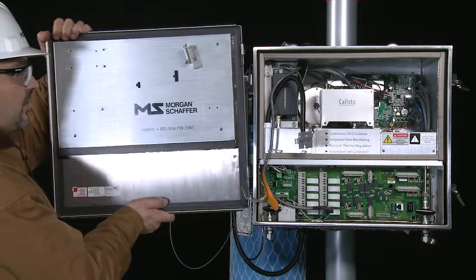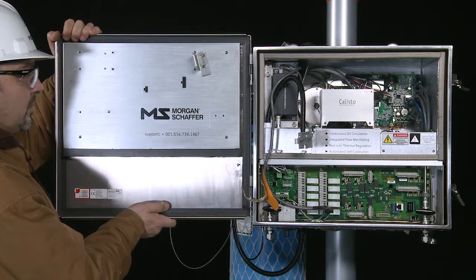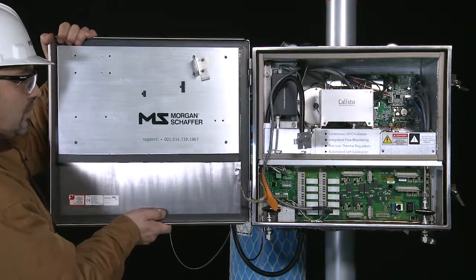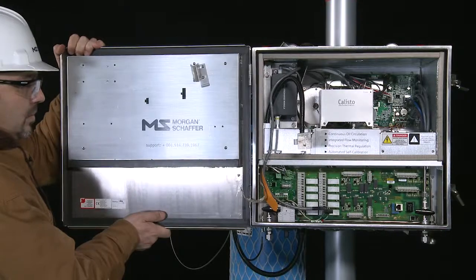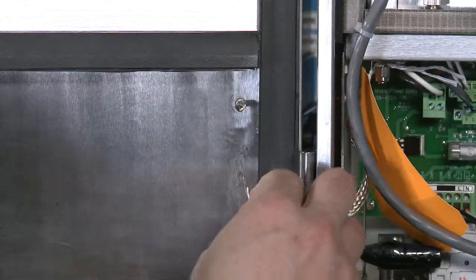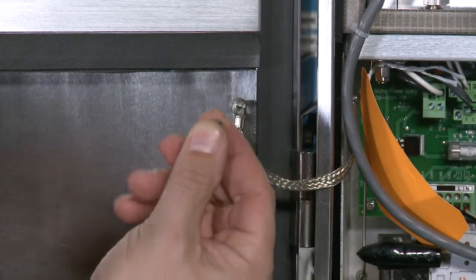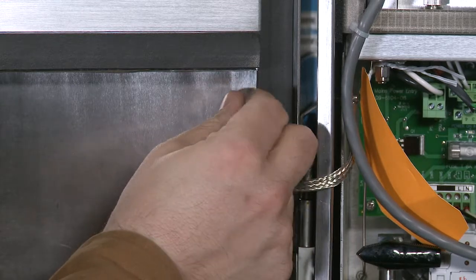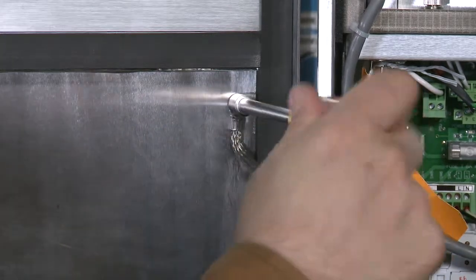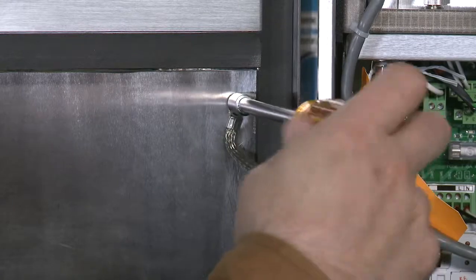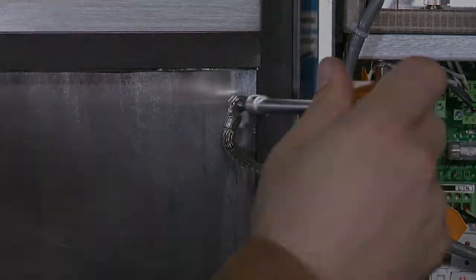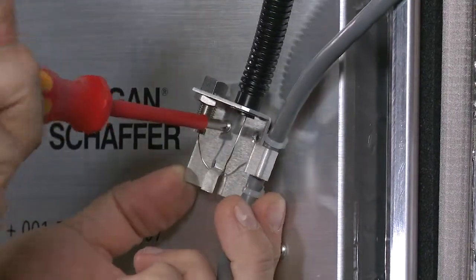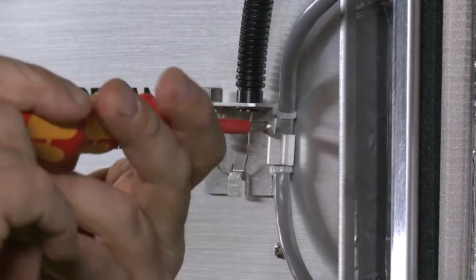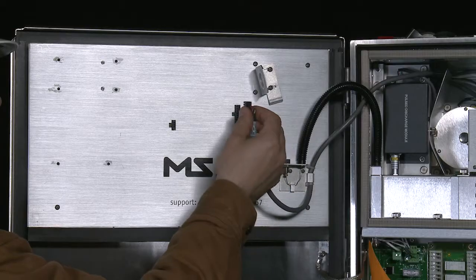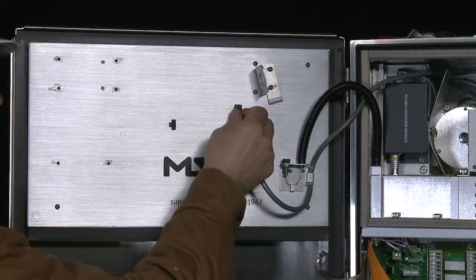Installing the door. Take the new door and, if needed, use a lubricant on the latch pins. Install the door by aligning both door pins on the enclosure hinges. Reinstall the door ground link using a 5/16" nut driver using the lock washer and the nut from the old door. Reinstall the bracket with the 2 screws using a Phillips No. 1 screwdriver. Reconnect the display cable.